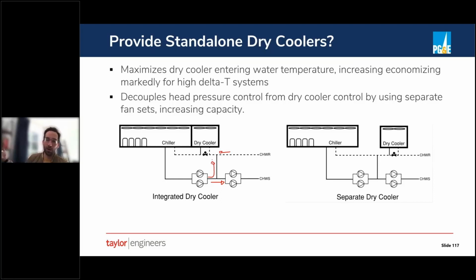And the lower you have the temperature going into the dry cooler, the smaller percentage of the load in an integrated condition that the dry cooler can do, meaning you're doing more of the cooling using your chiller. That issue is eliminated entirely if you have a separate dry cooler, because the temperature coming back at the dry cooler is the actual chilled water return temperature from the load. And it's only after the dry cooler that you're taking any of the flow that's going through the decoupler and blending it with the return.